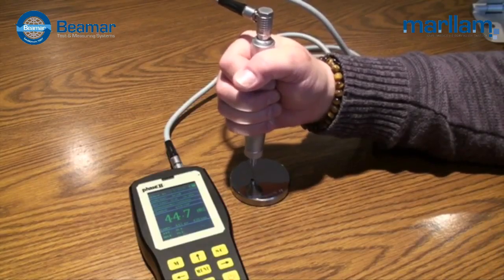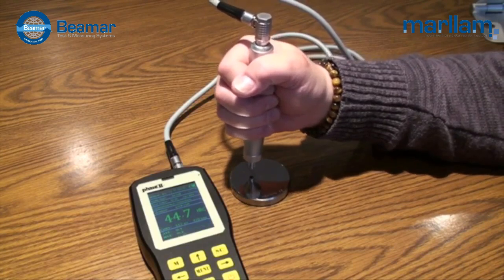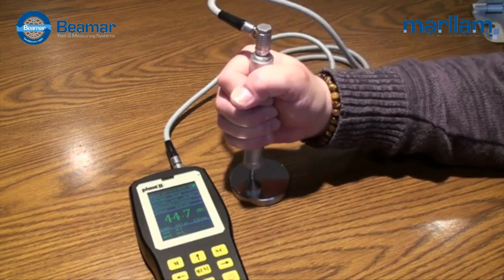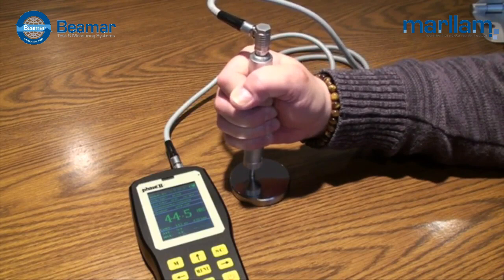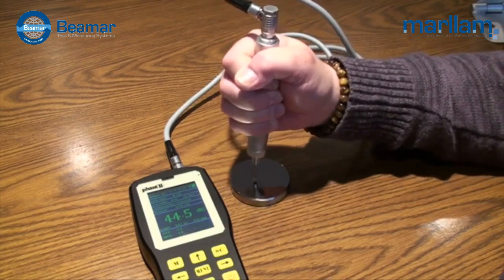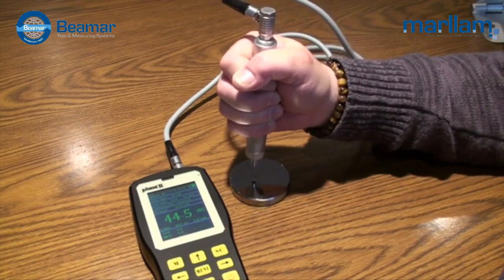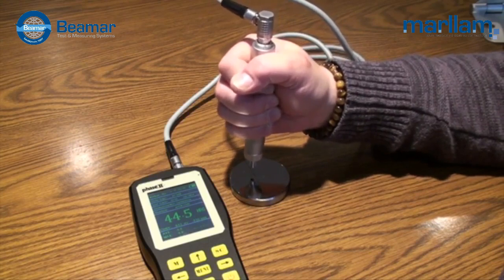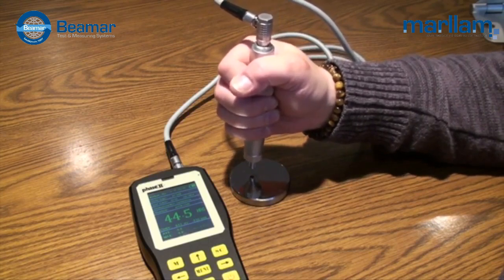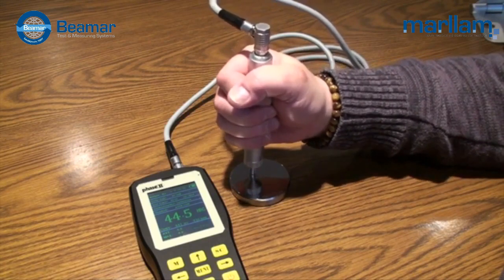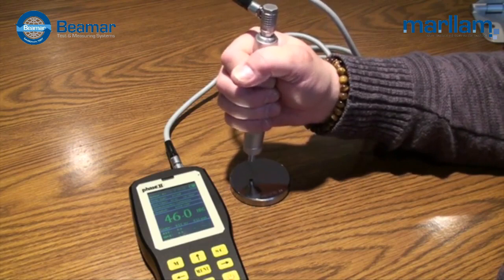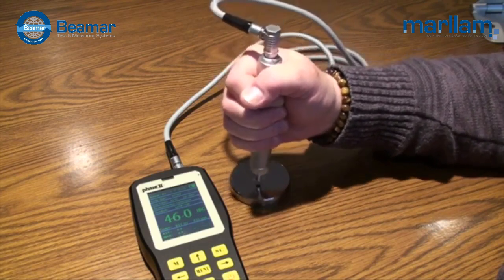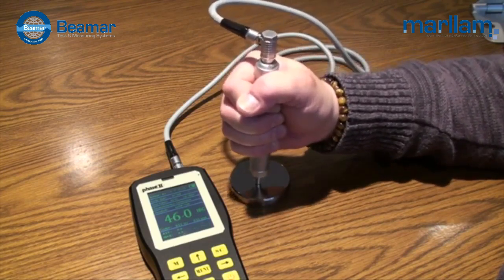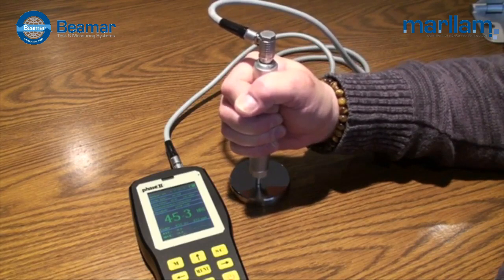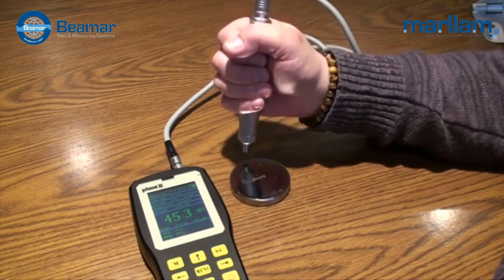To take a test, hold the probe in a tight fist. Press the probe straight down flat on the surface of your part and hold very steady until the unit beeps and gives the hardness value on the display. Immediately lift the probe off the surface, then ready to take the next test. Proper use of the probe will help you to achieve correct, repeatable results. Continue testing for average. This procedure may take a few minutes of practice, but should come to you easily after taking tests on the supplied calibration block.